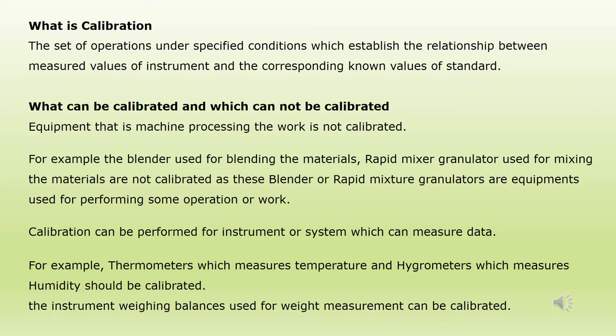What can be calibrated and what cannot be calibrated? Equipment or machines performing work are not calibrated. For example, a blender used for blending materials or a rapid mixer granulator used for mixing are not calibrated, as these are equipment used for performing operations. Calibration is performed for instruments or systems which measure data, such as thermometers which measure temperature and hygrometers which measure humidity.